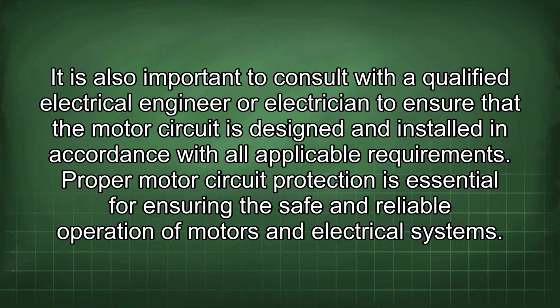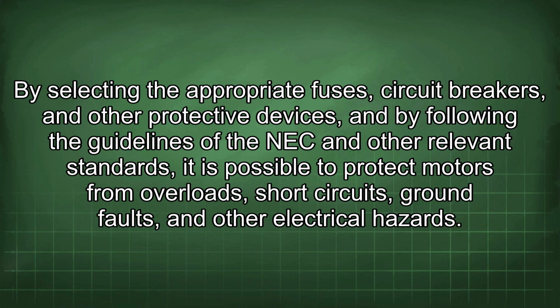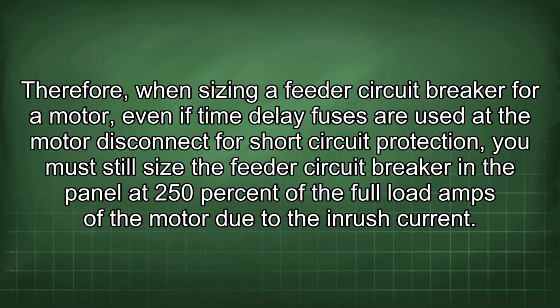Proper motor circuit protection is essential for ensuring the safe and reliable operation of motors and electrical systems. By selecting the appropriate fuses, circuit breakers, and other protective devices, and by following the guidelines of the NEC and other relevant standards, it is possible to protect motors from overloads, short circuits, ground faults, and other electrical hazards. Therefore, when sizing a feeder circuit breaker for a motor, even if time delay fuses are used at the motor disconnect for short circuit protection, you must still size the feeder circuit breaker in the panel at 250% of the full load amps of the motor due to the inrush current.